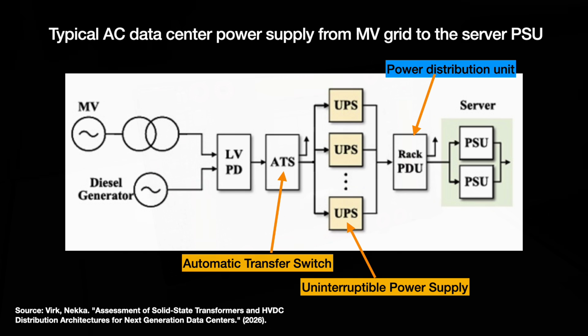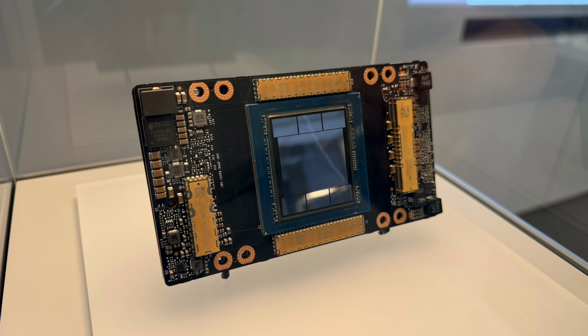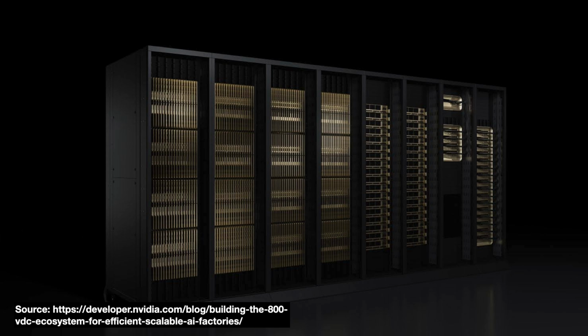Modern AI racks, however, need way more power, like 1 megawatt. Power is equal to voltage times current. Bigger current necessitates having a thicker copper wire. So either we can have a thicker copper wire at lower voltage or a thinner copper wire at higher voltage. At 1 megawatt, with the existing 54-volt rack architecture, you may need up to 200 kilograms of copper bus bars, which is expensive and too heavy considering that this is space that is not generating revenue for the data center.